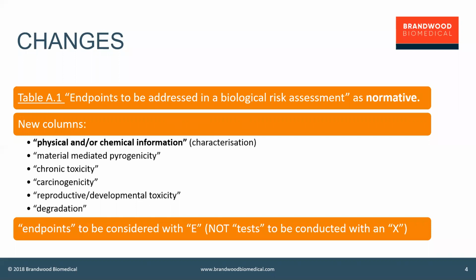So historically, the Annex A, where Table A.1 lives, has been informative. That is, it just speaks to the rest of the standard, but it's not enforceable. As a normative annex, the content of Table A.1 is now part of the enforceable standard. So if somebody wishes to claim that their medical device biological evaluation is compliant with this standard, then it will have to be compliant with Table A.1, and you will have to demonstrate that you have addressed the endpoints that are nominated in the table.